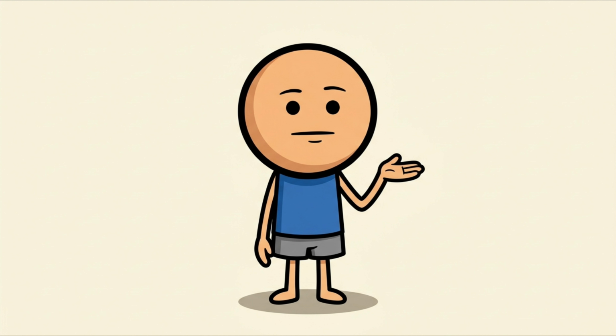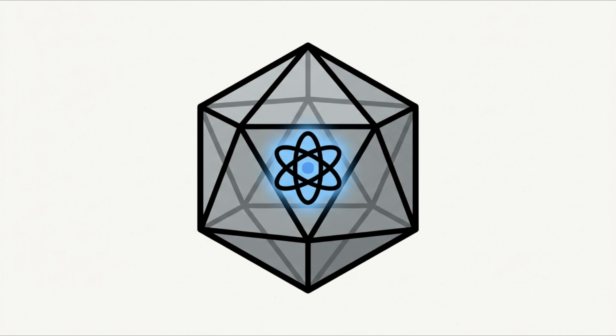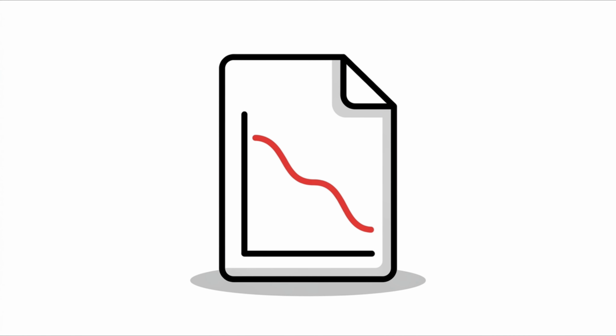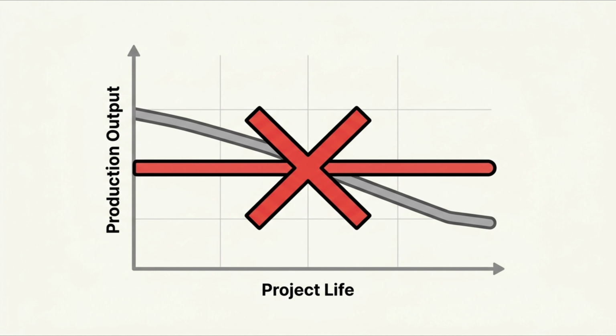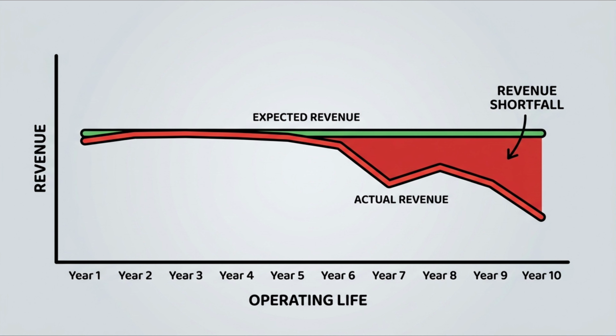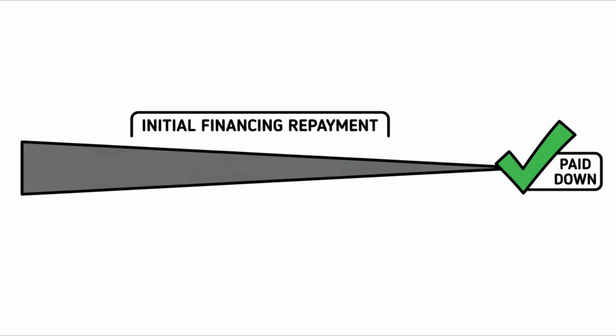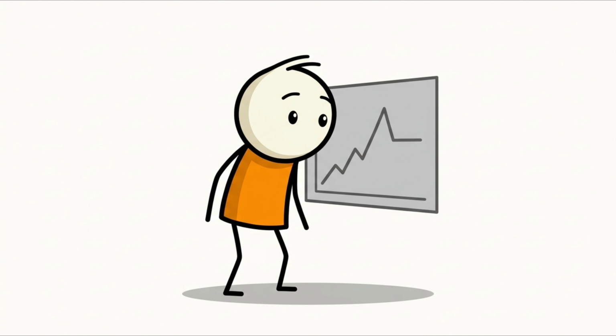This isn't a malfunction. It's baked into the physics of the silicon itself, and every serious financial model for a solar farm has to account for this steadily declining output curve rather than assuming flat production for the life of the project. A farm modeled optimistically on flat output projections can come up significantly short of expected revenue by the back half of its operating life, precisely the years when the initial financing has typically been paid down and investors are expecting the strongest free cash flow.